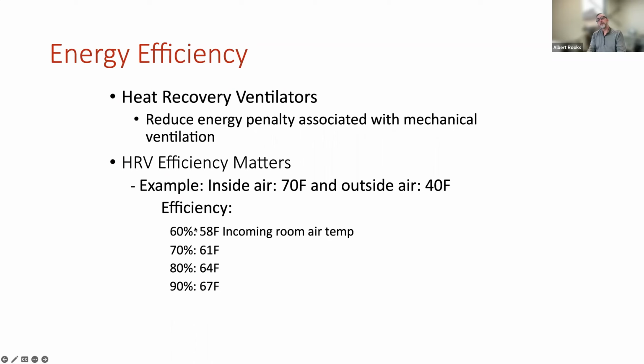And if you feel 58-degree airflow on your skin, it feels cold, right? It's just not a super pleasant feeling. And then if you look at a building and say, okay, I've got a 1,200 square foot apartment and my ventilation rate I'm going to use is 70 CFM as a number, essentially I'm going to be pushing 58-degree air into that apartment 24/7, as long as it's 40 degrees outside. And so that's unconditioned, that's lightly conditioned air, and I'll have to reheat that back up to 70, right? So there's an energy penalty there, and there's a feeling on your skin of cold air.